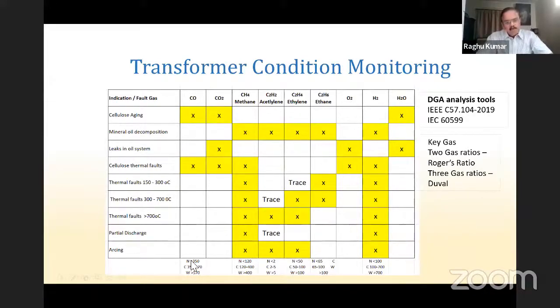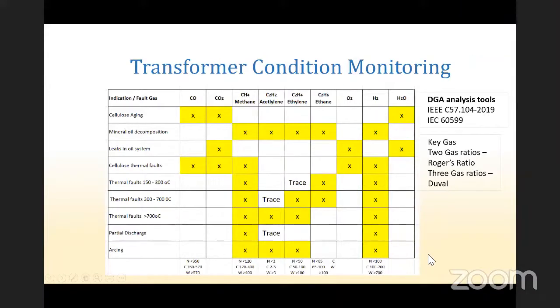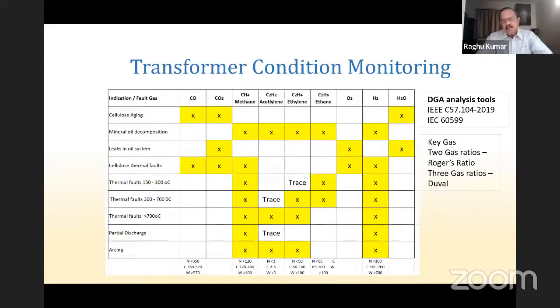There are also normal values given in IEEE standards. For example, for hydrogen, 100 ppm is a normal value, the 100 to 700 range is a caution value, and above 700 is a warning. But IEEE is very, very conservative, so this 100 is not always practical. It is load dependent: in summer the hydrogen level increases, in winter it comes down. So we used to keep up to 200, 250 as normal, and in winter it will definitely come down. And how do we find out what the fault is?